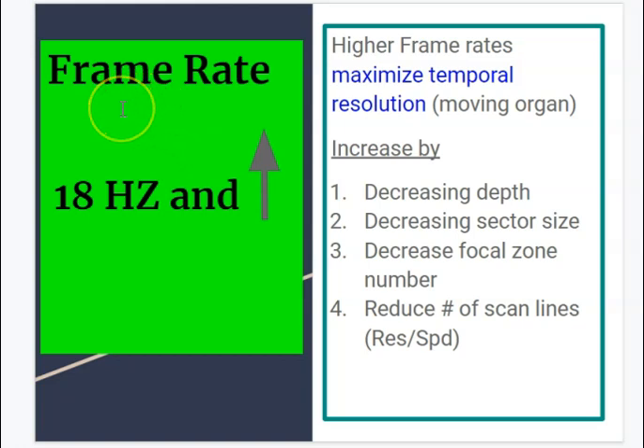For cardiac imaging, if you talk to most people out there, we want to keep our frame rate at 18 hertz and up. That seems to be where you don't see a jumpy image, so to speak. You see something that's smoothly moving as one image, not jumping around on the screen. So higher frame rates maximize temporal resolution. We can increase our frame rate by keeping our depth as shallow as possible, and decreasing our sector size, our box size, because that's going to reduce our scan lines and therefore increase our frame rate. Decrease our focal zone, and make sure we put our focal zone where we are actually scanning. A lot of people forget about that. And again, reduce the number of scan lines.